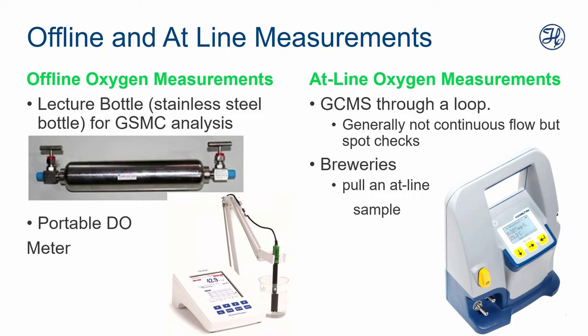There are four ways that oxygen is measured within a bioprocess. The first is what we call offline measurements. Examples of this are something called a lecture bottle. It's a stainless steel bottle. It does GCMS analysis. It grabs headspace oxygen off. Remember, the partial pressure of oxygen in the headspace should equal what's dissolved in an equilibrium state. So if you take an oxygen sample out of the bioreactor and you run it over to GCMS, that should give you a good indication of where your oxygen measurements are.